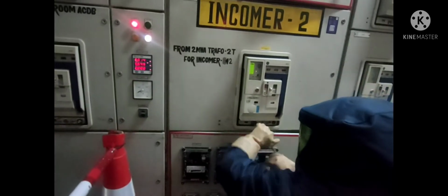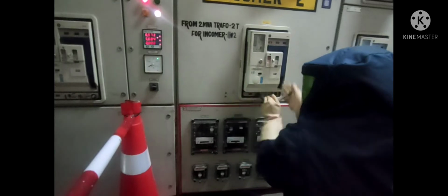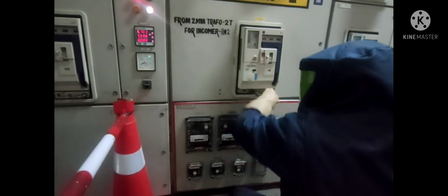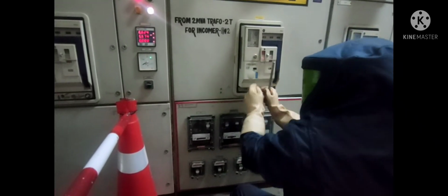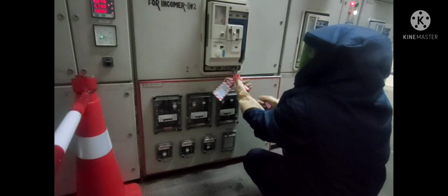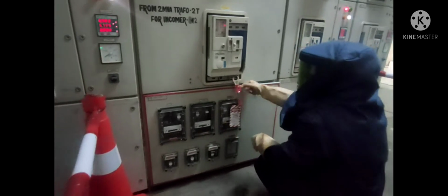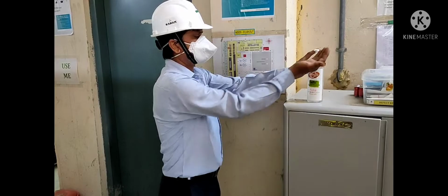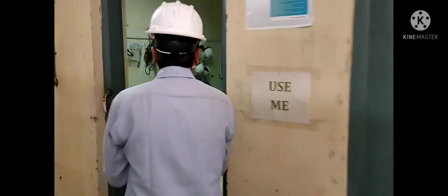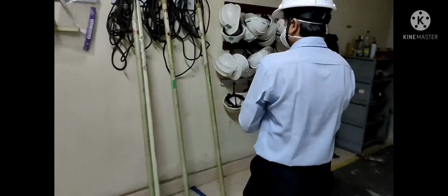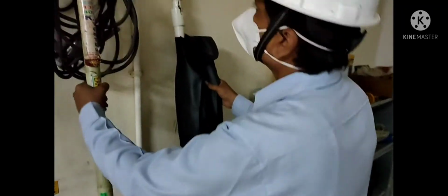To stop any backfeed, we are applying LOTO on the load end. For that, we are racking out the air circuit breaker. To work in the power cable chamber, we have to use a live line detector and earthing rod. For that, first we will check whether these devices are tagged safe for use or not.